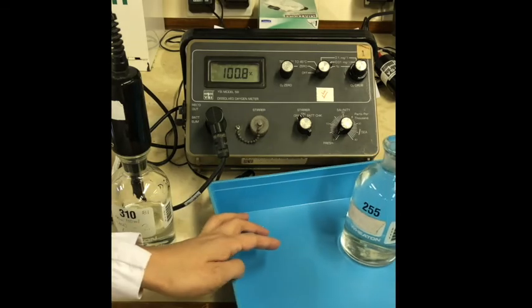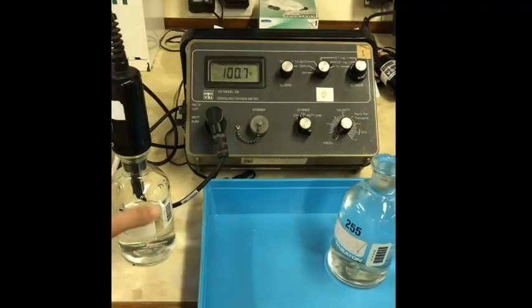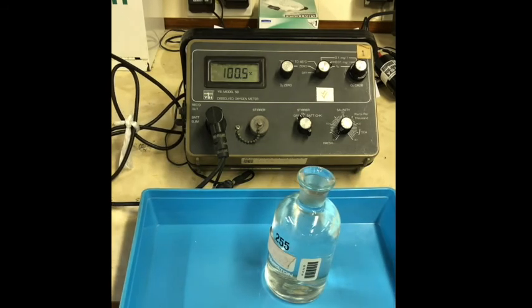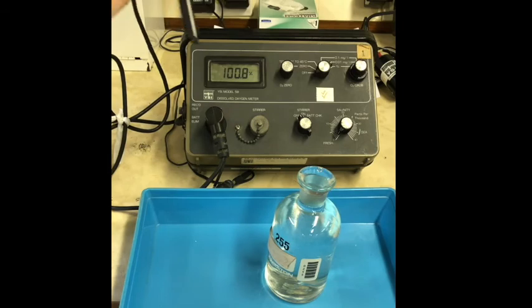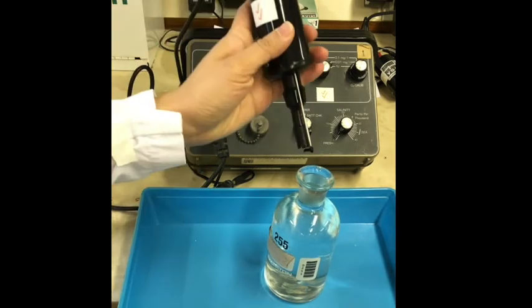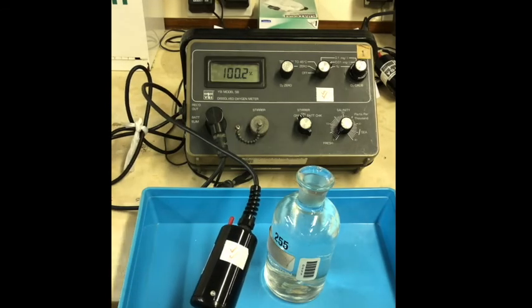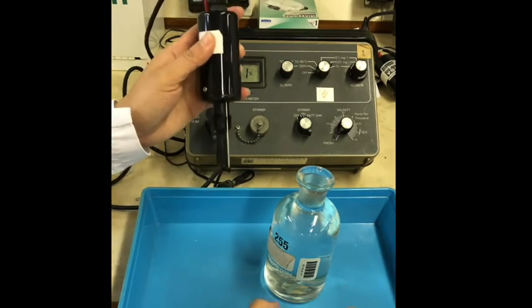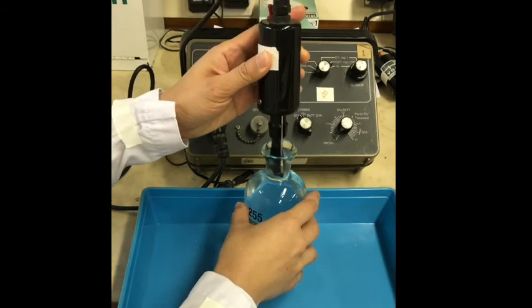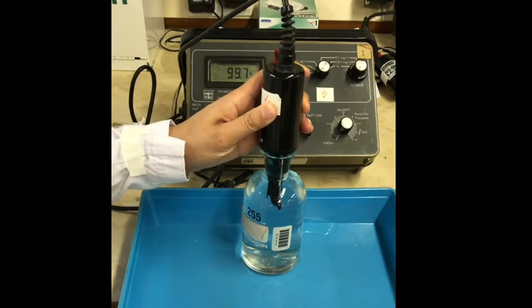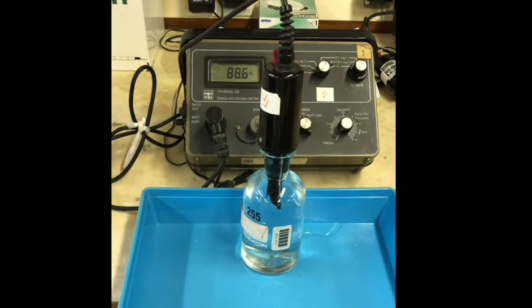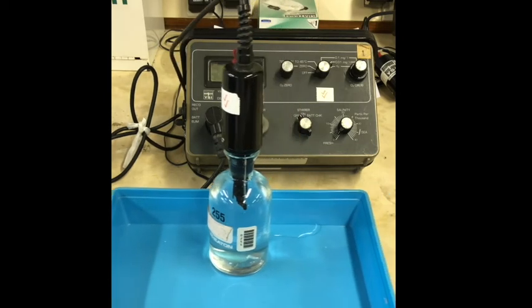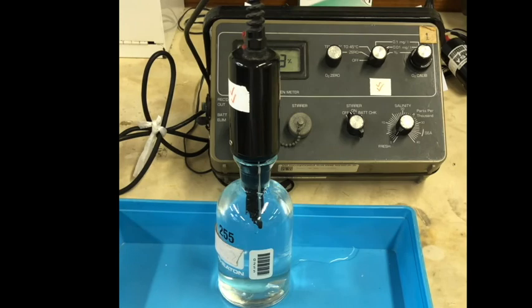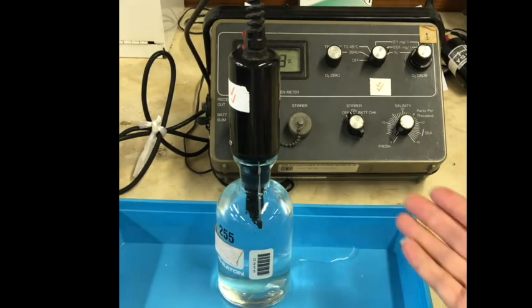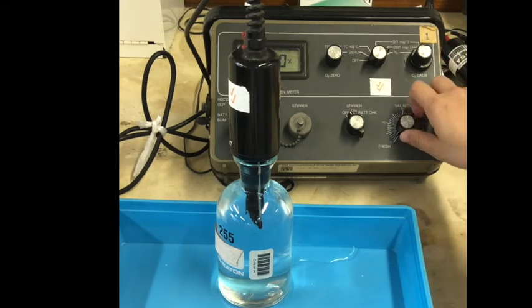Place the tray under the BOD bottle containing the sample water. The water sample will overflow when you insert the electrode into the sample bottle. Insert the electrode into the BOD bottle. Make sure no gas bubble is trapped inside the BOD bottle. And then set the salinity of the water sample. The salinity of the water sample was about 28 ppt.